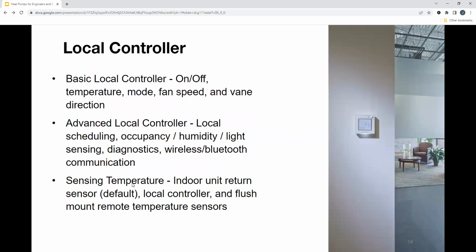So, different types of local controllers here. If you install the heat pump system and turned it on, it would run how it is. It would run on return air temperature, right? Ways of sensing temperature is either the return, where your local controller has a temperature sensor, or, if you don't need any local control at that space, you can also include temperature sensors or thermistors. If you installed any of those, they would work on their own. But basic control, pretty straightforward. There's 6 functions. You have your on-off, you have your temperature, mode, fan speed, and vane direction, right? Pretty basic, on the wall, local occupants can figure out what temperatures they're most comfortable at.